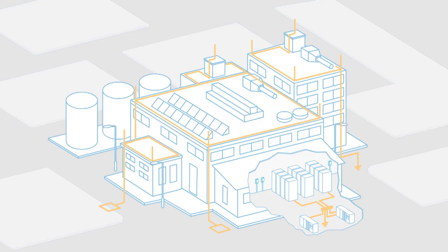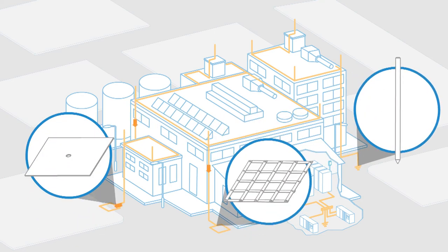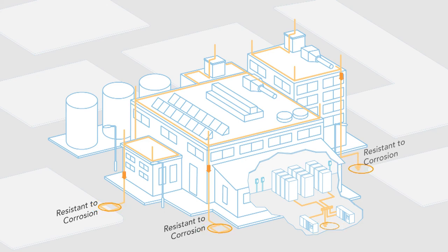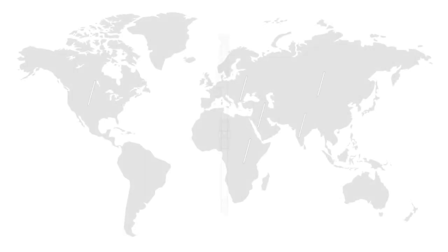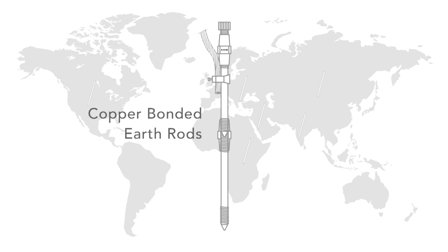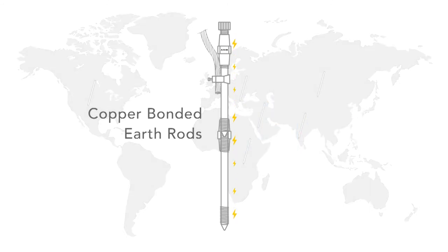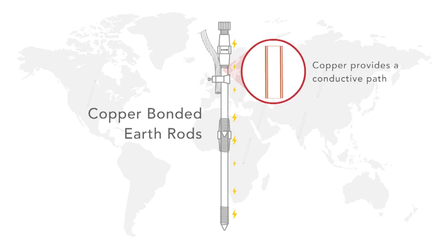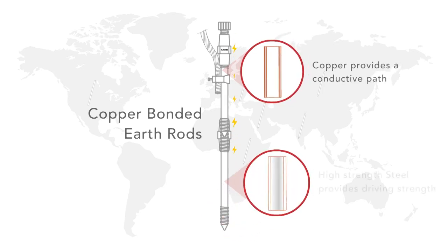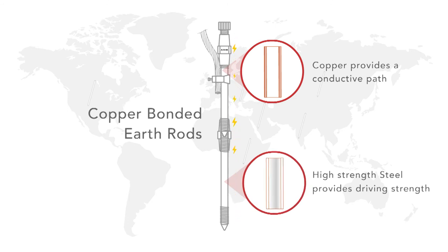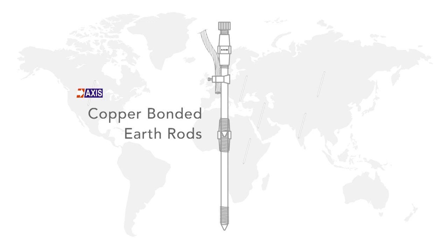Earth Termination: An earth electrode should provide low electrical resistance with the earth to allow for the dissipation of currents. It should also be resistant to corrosion because it will be buried underground for a long period of time. Worldwide, one of the most popular earth electrodes are copper bonded earth rods, which comply with IEC 62561 part 2. Since electricity is a surface phenomenon, the copper layer allows for a conductive path while the inner core of high-strength steel provides the strength required for driving the rod into the ground. Axis copper bonded earth rods have been approved by utilities across the world and continue to be popular due to their consistently high quality.